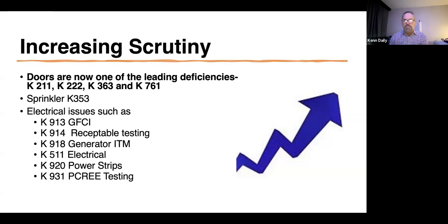I mean, that's the ultimate penetration, is a door from one part of your building to the other, whether it's a smoke or fire barrier, it doesn't matter. They have to close, they have to latch, they have to have the pieces and parts all be present, the door can't be damaged, etc. So doors is the number one deficiency in the country, and Pennsylvania is no different.